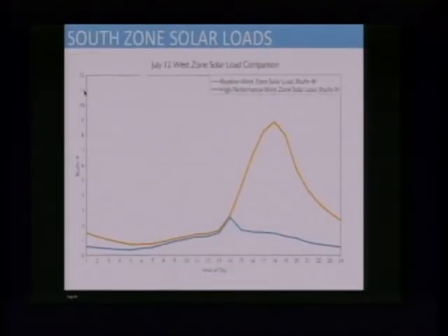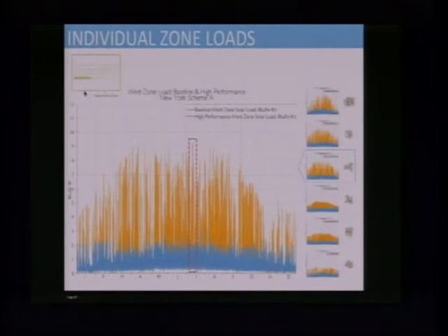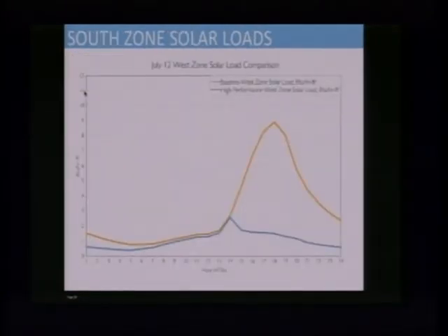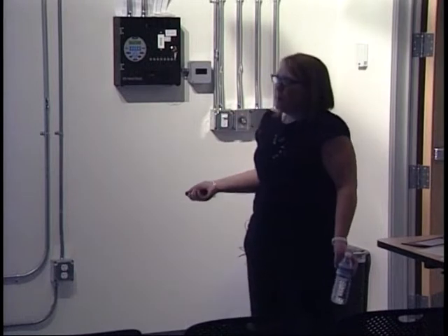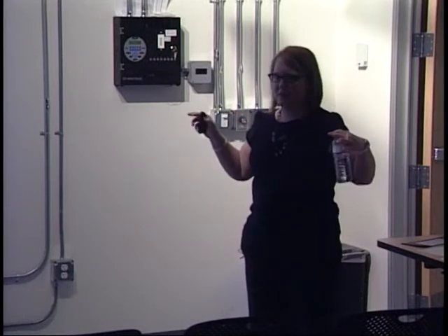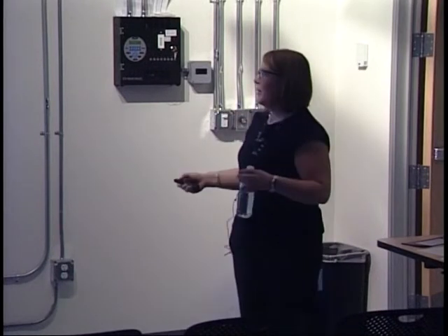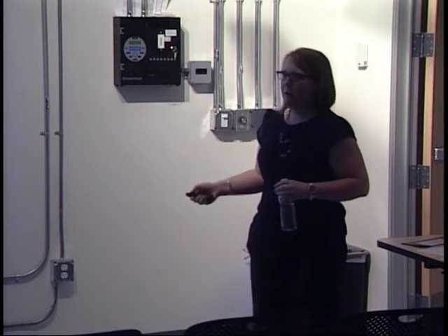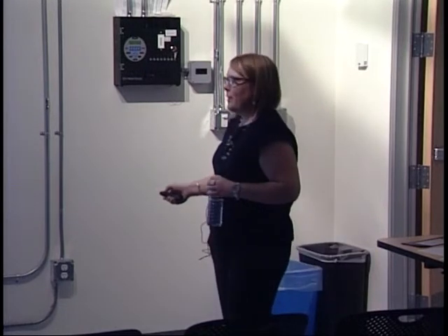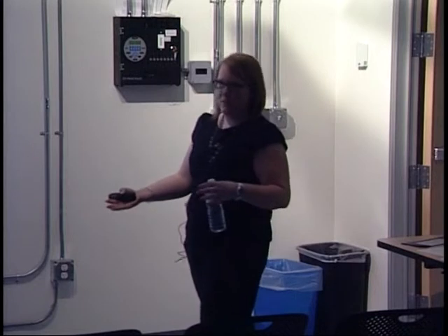Here's the peak day, going back to this graph. This one day is the peak day, so we've graphed it. You can see this huge peak in the afternoon, which makes sense since the afternoon sun comes around the west and makes the room really hot. The solar shading has the effect of just lopping off that peak. That's important because the radiant cooling panels can only keep up with so much load, and they can't keep up with this load. So it's important to lop that off, not to mention the displacement ventilation issue.